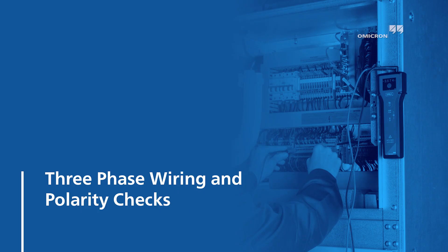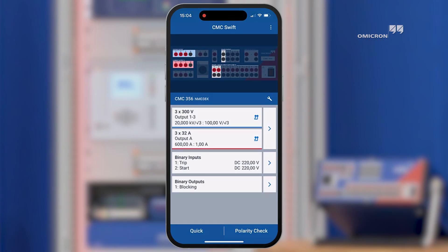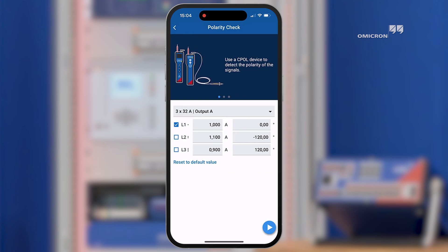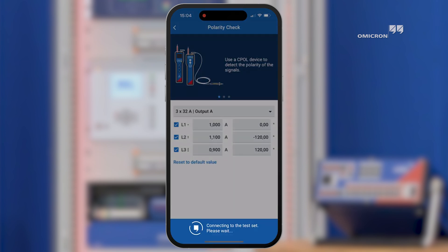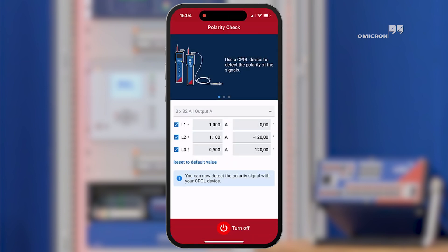Let us begin with the most interesting feature highlight of CMC Swift and explore together how to prepare a CMC test set for three-phase polarity checks. Three-phase polarity checks can be performed in combination with the new cPOL3 handheld polarity environment checker. You might be curious how this is working. The CMC test set generates a cPOL polarity check signal with additional phase identification information, commonly known as phase ID.